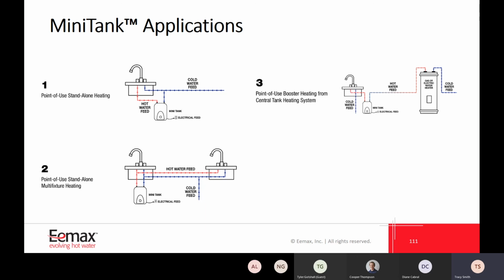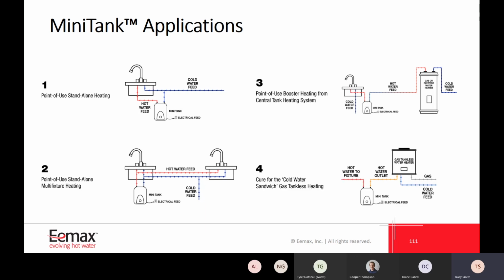You can have hot water instantly with a mini tank installed directly under the point of use. And in the case of a gas tankless water heater, we can eliminate the cold water sandwich with instantaneous hot water using a 6-gallon mini tank as a buffer tank in these installations. A lot of versatility with mini tanks.